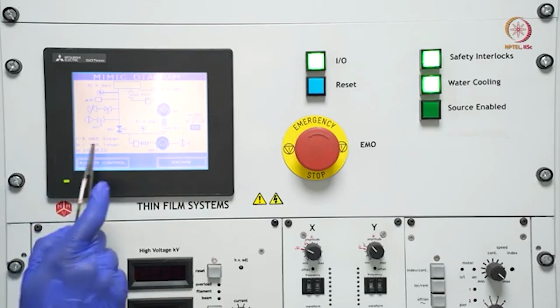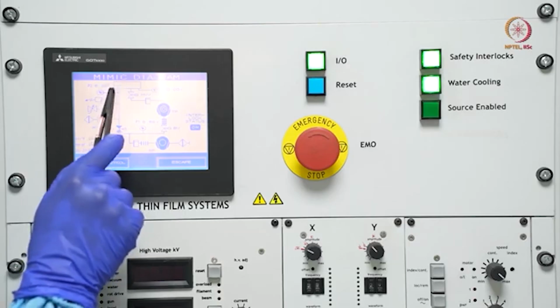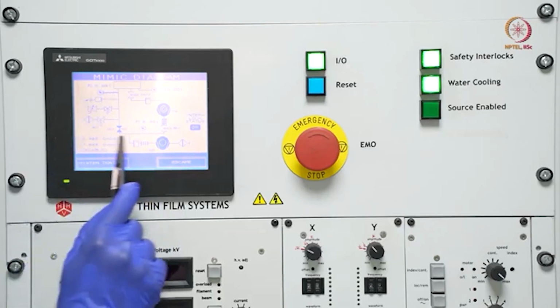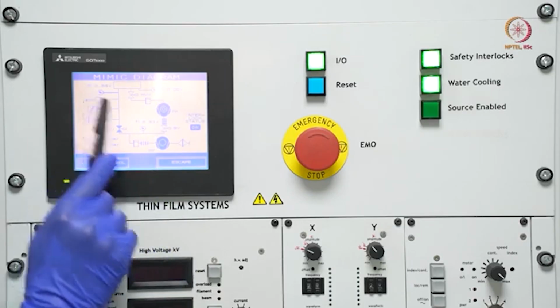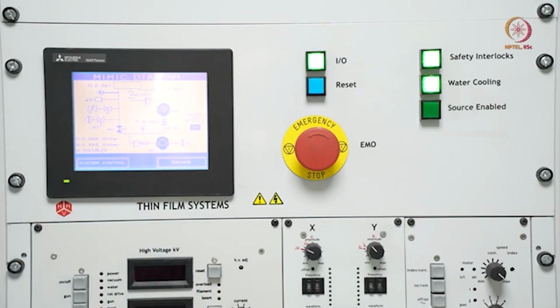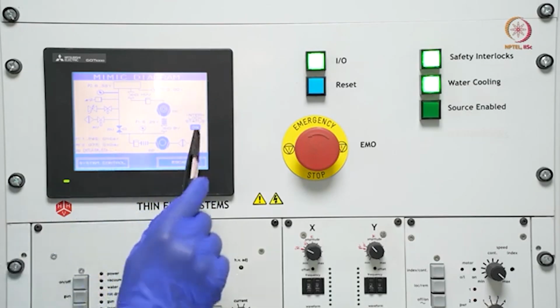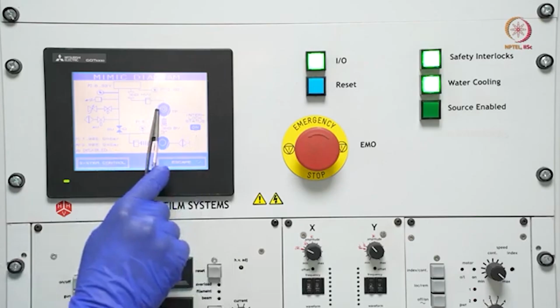Here you can see only P1 and P2 are active, so P2 is here. This is giving almost like a Pirani gauge connected near this line, and the other one is here in between the roughing and backing line, almost nearby this roughing pump. These two are giving the values now. So you can see here some volt is coming, that is the sensed voltage. That voltage is converted to pressure, and from there we are getting this value, some millibar. So here you can see the safety interlock is on, this is also on, this is ready basically, and this is also on. And now let us go to system control, because we can do everything from there only.